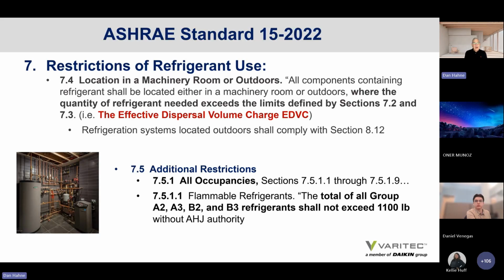There's language also on location in a machinery room or outdoors for variable refrigerant systems. All components containing refrigerant for a variable refrigerant system shall be located either in a machinery room or outdoors where the quantity of refrigerant needed exceeds the limits defined in section 7.2. And this is untenable for VRV. It defies its purpose. So standard 15 lists design strategies to help overcome this requirement.